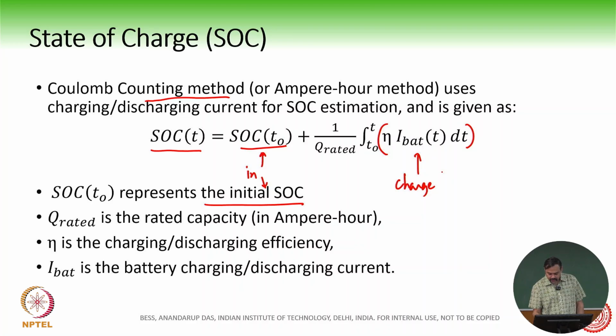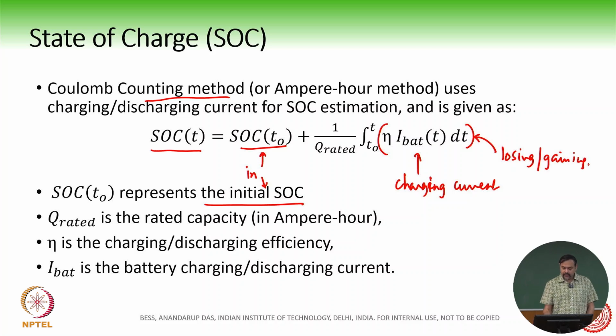So I is the charging current. This is how much you are losing or gaining, divided by the Q rated, as a percentage of Q rated. Of course there is an efficiency, because charging or discharging does not take place at 100% efficiency. So this is how the state of charge at any instant of time t can be obtained, provided you know accurately what is the initial SOC.